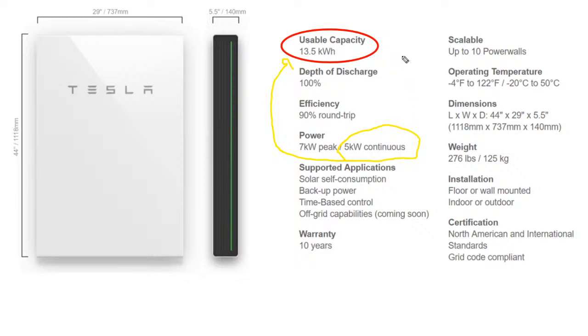Now, could you discharge a lithium ion battery faster than that? Probably. But is it a good idea? No. Just like with a lead acid battery, the faster you discharge the battery, the worse it is for it fundamentally. That does not change with lithium ion versus lead acid, except that lithium ion is a little bit tougher. Instead of really not being able to handle less than a 6 hour or 5 hour discharge rate with lead acid - beyond that you've done a bad job with your design - with lithium ion, it's closer to 2 hours, 2.5 hours. So Tesla is limiting the maximum discharge rate of their battery to about 2.5 hours.